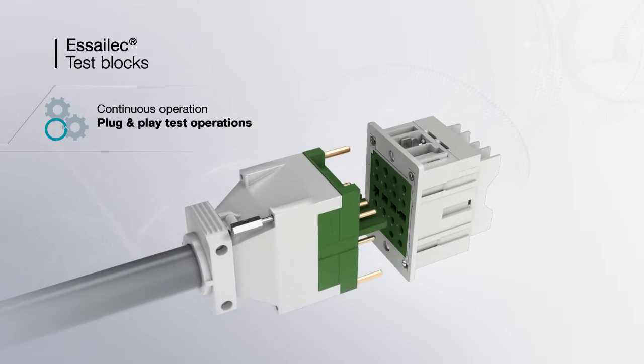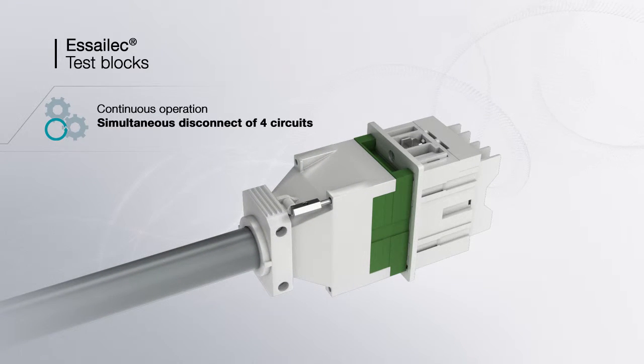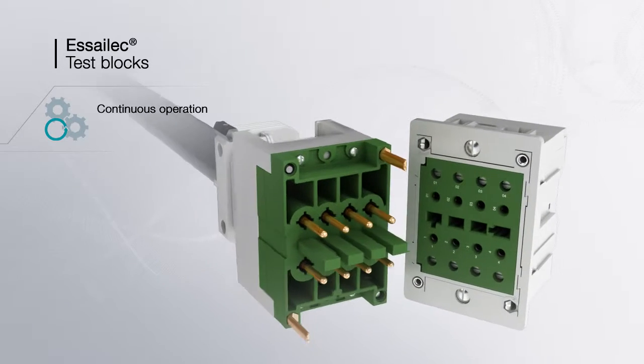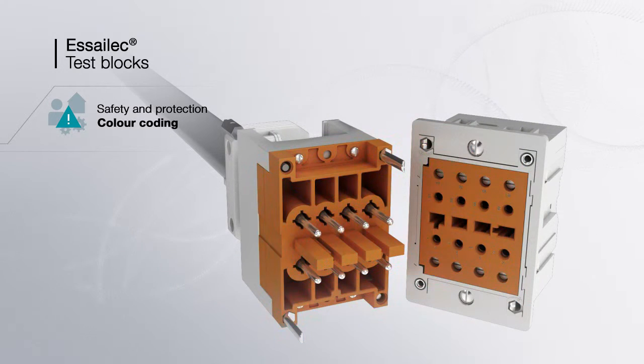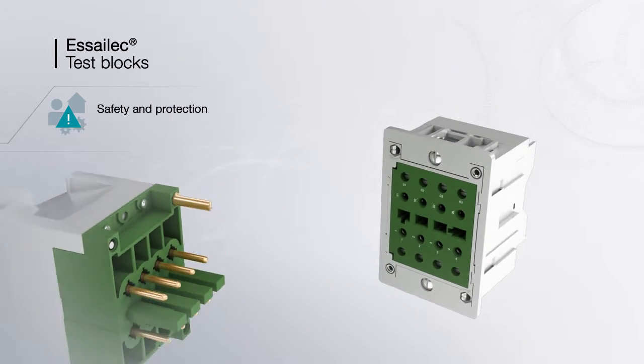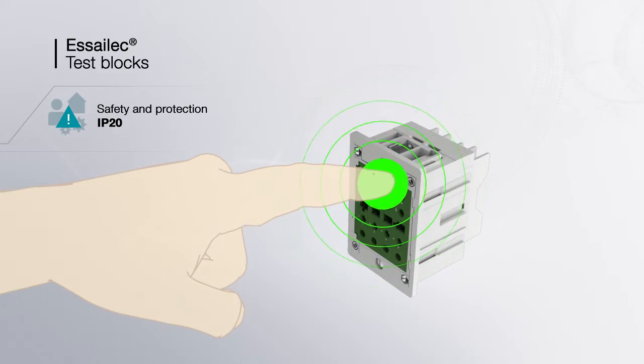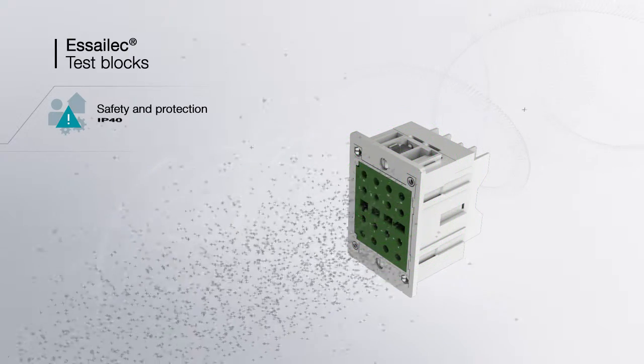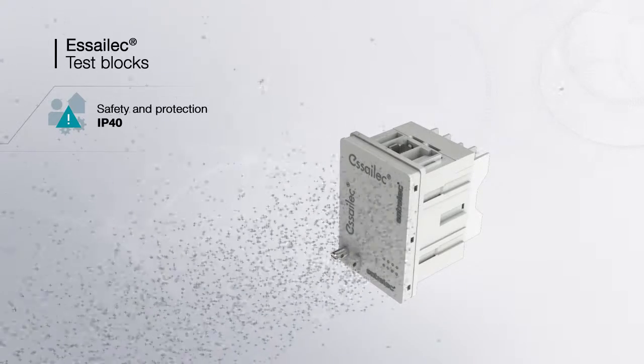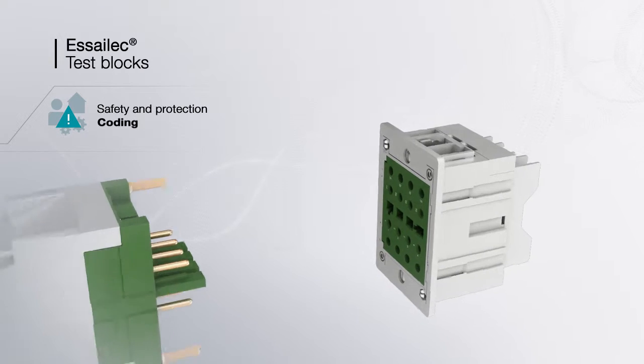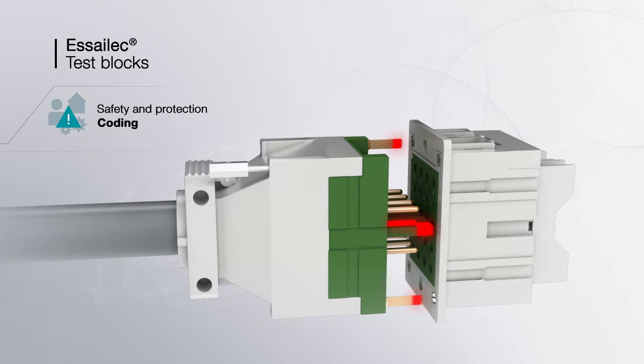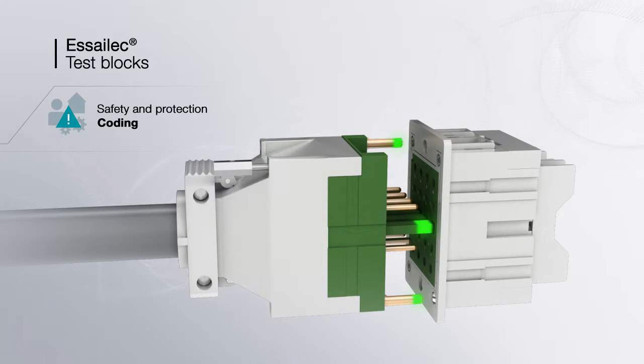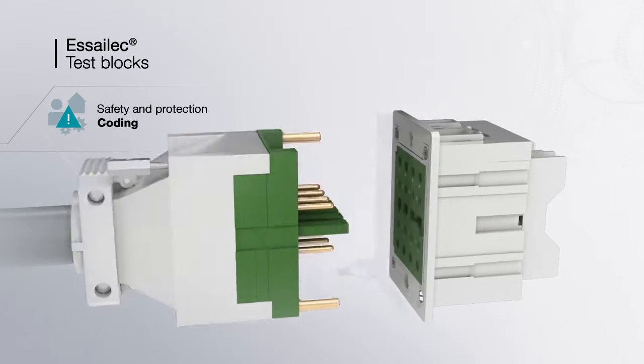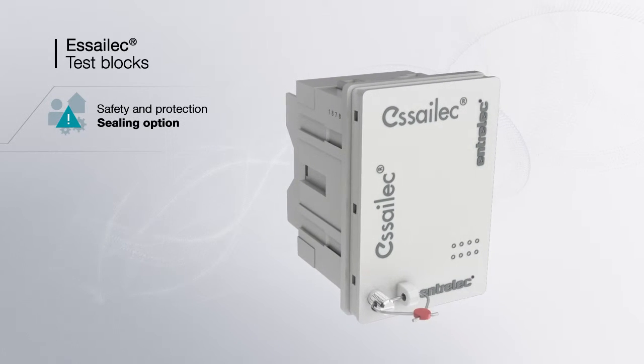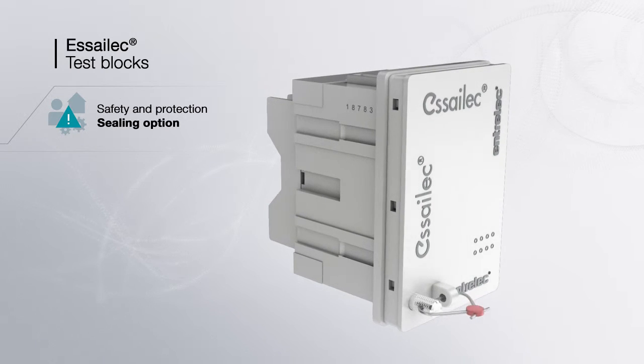The Essailec plug and play principle allows fast and easy test operations, simultaneously on 4 circuits. Marking and color coding ease circuit identification. IP20 touchproof socket and IP40 protection with the lid. The coding systems prevent reverse mounting or product mix between current and voltage Essailec devices. During normal operation, the lid can be sealed to prevent unauthorized access.